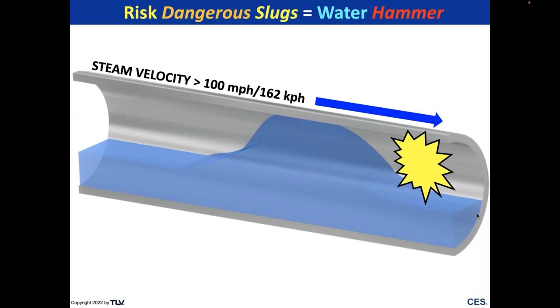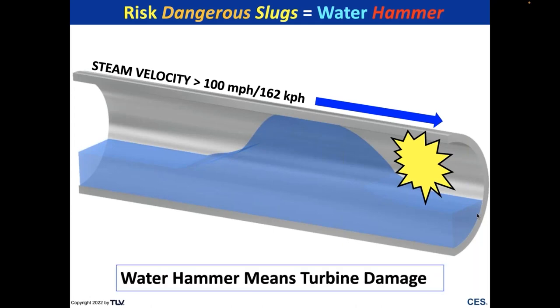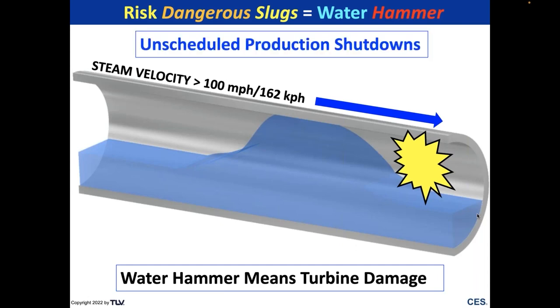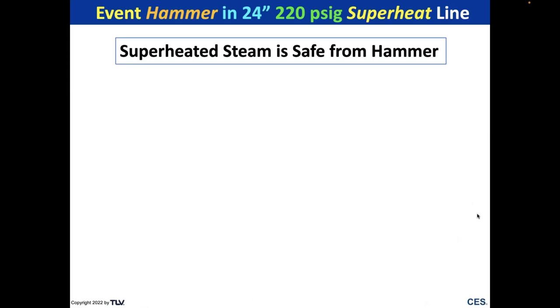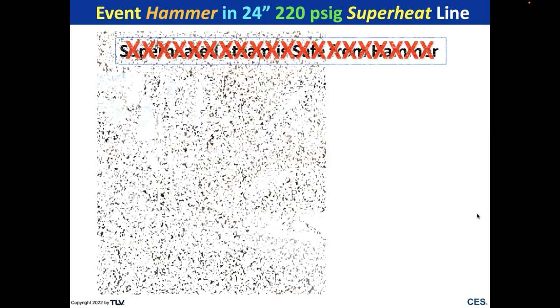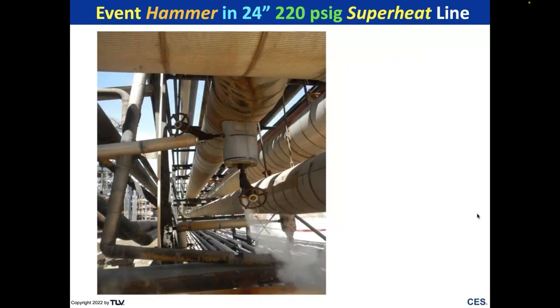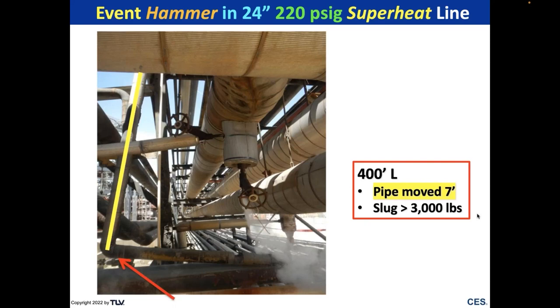Steam velocity is typically 100 miles an hour — 162 kilometers per hour or more. If you build up water into a slug across the cross-sectional area, that velocity can be over 200 miles per hour. Water hammer equates to turbine damage, which can equate to an unscheduled production shutdown. Lots of turbines can be damaged — not only the main compressors but also lube oil pumps. There's another fallacy: that superheated steam is safe from hammer. Here's a plant where a 400-foot length of 24-inch pipe on a 220 psig superheat line moved seven feet from a slug estimated over 3,000 pounds — a force that moved 250,000 pounds of pipe.